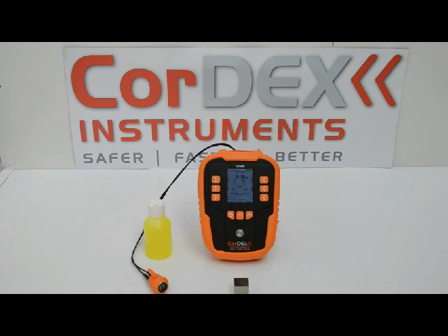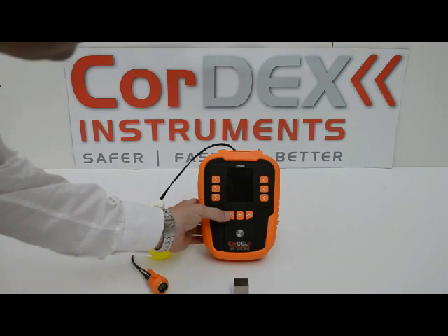Using an ASTM stainless steel calibration block with a concealed flat bottom hole, the new intrinsically safe UT5000 ultrasonic thickness gauge from CORDEX Instruments will now demonstrate its ability to detect this void easily from two different axes.